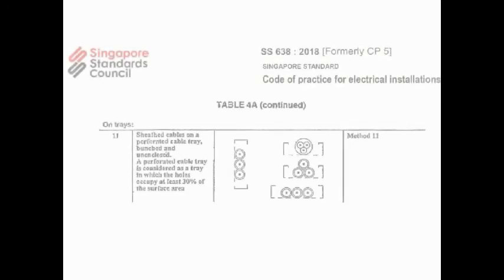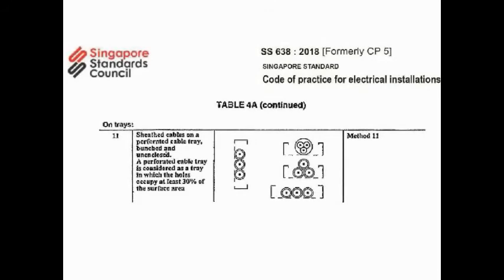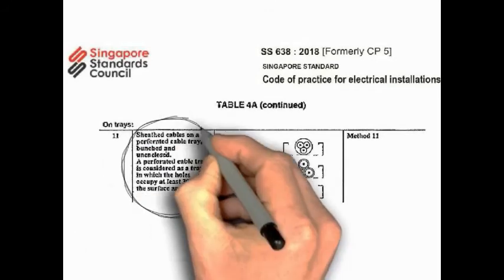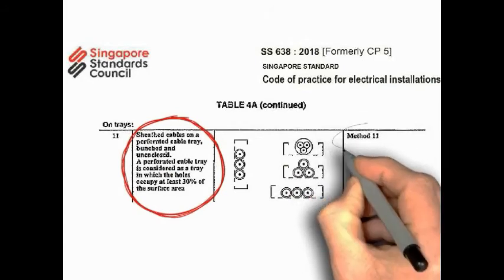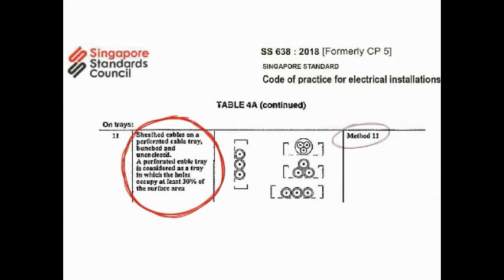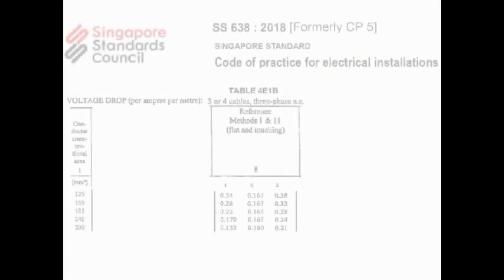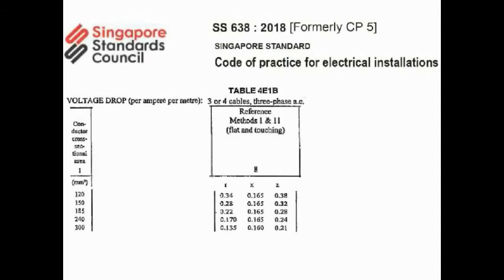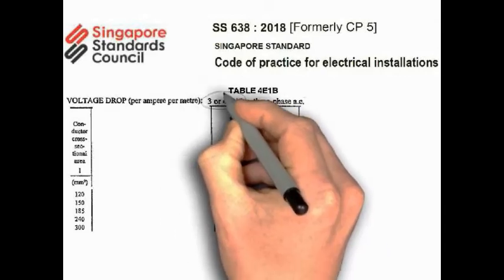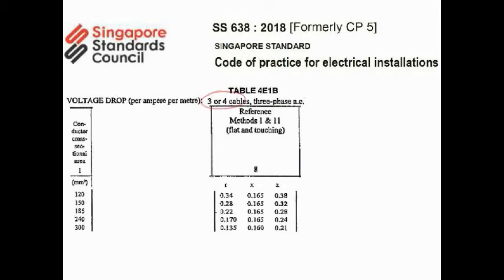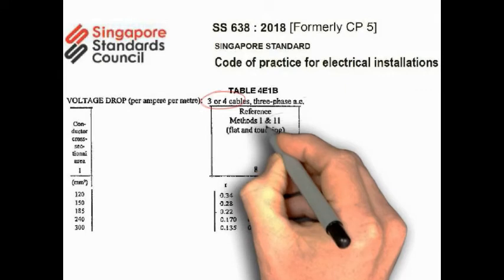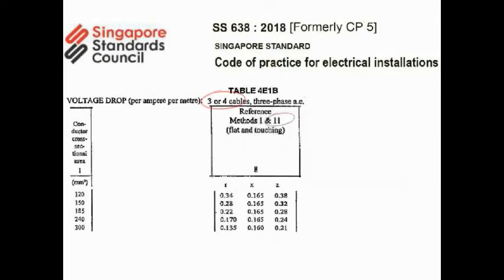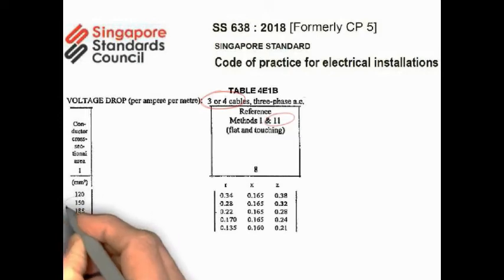First, we go to table 4A and identify based on the cable installation method. Using the perforated cable tray, and this will bring us to the selection of method 11. Now we go to table 4E1B to estimate our voltage drop. First, we identify the number of cables. For this illustration, we're going to use three or four cables as this is a typical three-phase circuit. From our chart earlier, we see that using the perforated cable tray brings us to installation method 11.